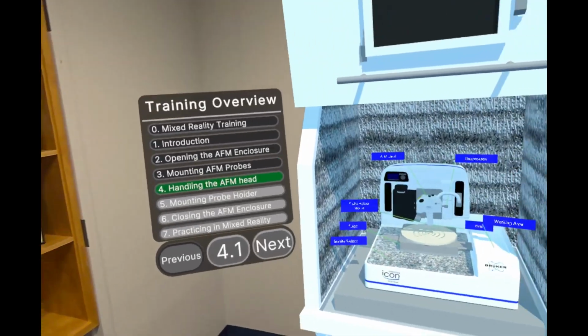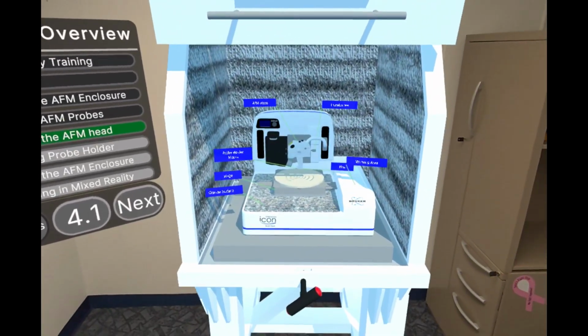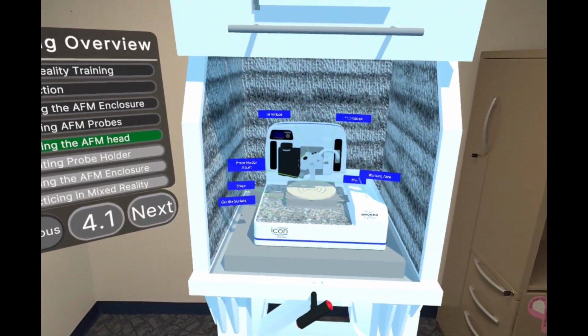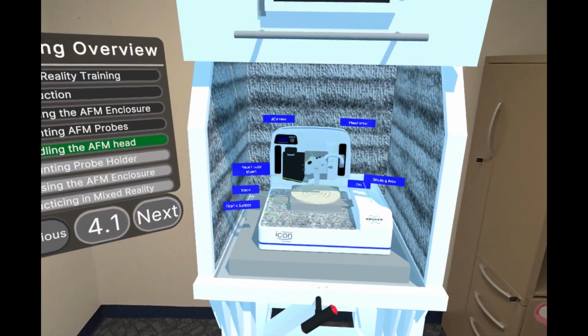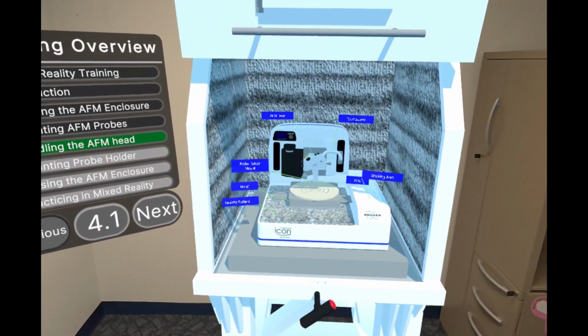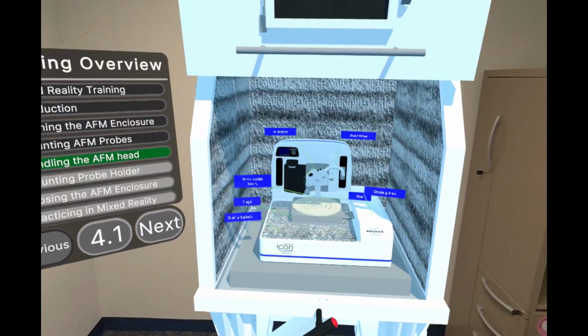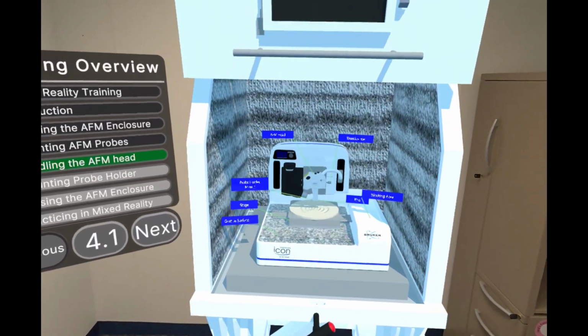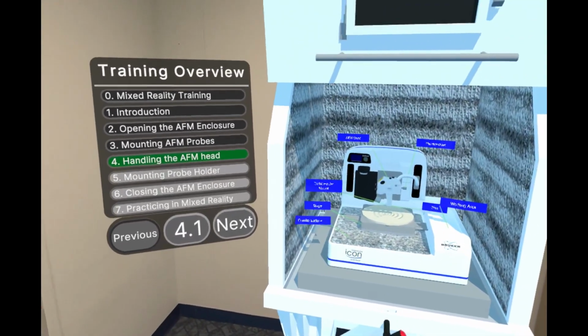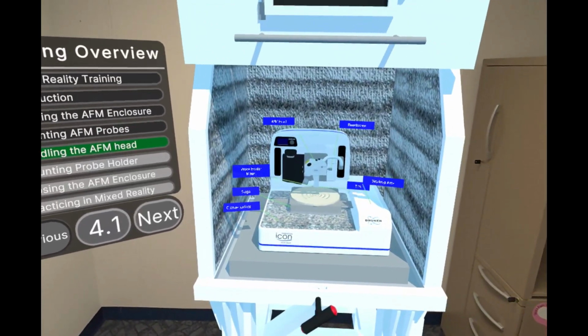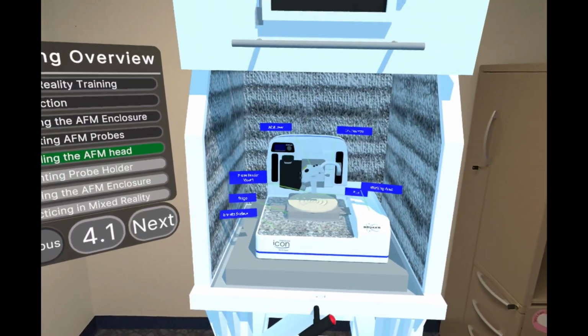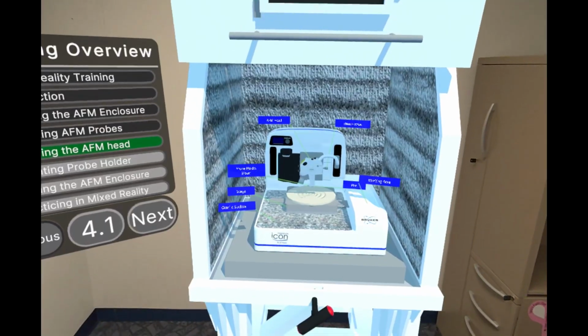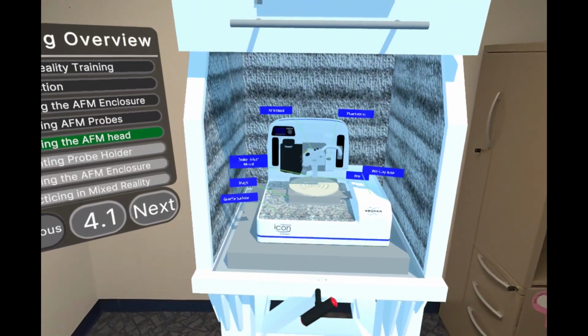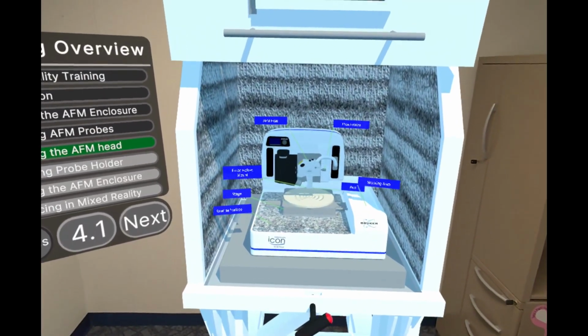The AFM stage uses the entirety of that granite surface for moving in X and Y. Use the raised working area on the right of the AFM or the AFM computer table to place anything you need for your work. Another way the AFM can be damaged is when there is a thick or tall sample on the stage. It is possible to crash the AFM head into a sample when it is on the stage and the user is navigating in X and Y without enough Z clearance.